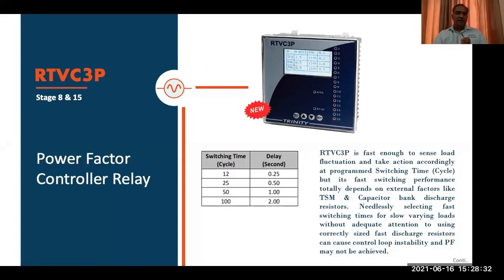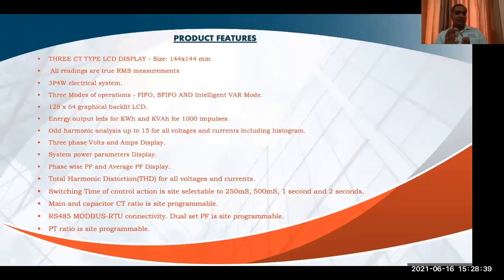And this relay, because of the big display it has, also gives you all the measurements, like your basic current and power measurement, your harmonics up to 15th level, voltage and current, all 3 phases of voltage, current, powers, energies, PF, THDs, everything is there in this relay. And it is both HT, LT, CTPT programmable. And you can also set a dual PF in this relay. It's a dual stage programming relay, and it is available in 8 and 15 stage.